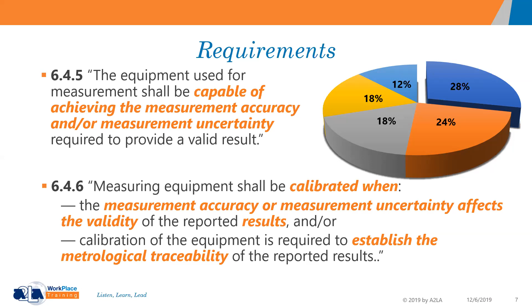So 6.4.5, what have we observed as assessors? How have laboratories evaluated their ability to achieve the accuracy and uncertainty in the calibration? So what are we seeing? First and foremost, most of the time, we're not seeing that calibrations are being performed across the entire range of the unit where it's being used. They calibrate it, for example, up to 3 keV when it's being used up to 15 keV, or other units of measurement. Or, as you see in the illustration here of the spectrum, this optical emission spectroscopy output, they don't calibrate all the points. They calibrate it at 550 nanometer wavelength or something like that.